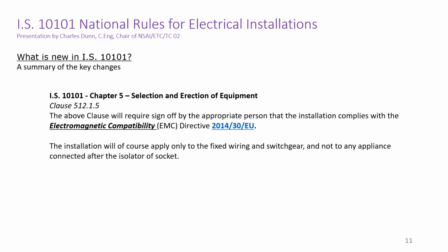Moving on to Chapter 5, Selection and Erection of Equipment, Clause 512.1.5, we see that this clause will require sign-off by the appropriate person that the installation complies with the Electromagnetic Compatibility Directive, the EMC Directive 2014/30/EU. The EMC Directive has applied for many years to equipment plugged in or connected beyond the isolator, so this clause will apply now to the fixed wiring installation. The responsible person may be the designer or in some cases the electrical contractor, where he is responsible for both the design and installation of the wiring.